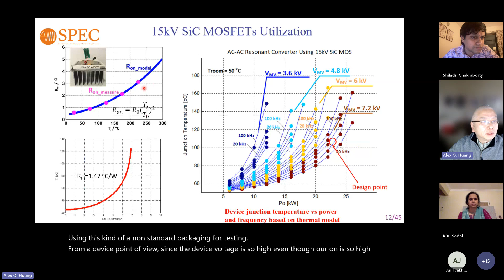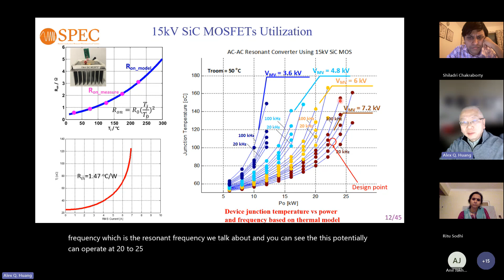The important thing is device voltage utilization - if you can increase the voltage, the same power will mean much less current. This is the optimization chart showing the utilization of the devices. What is changing is the switching frequency, which is the resonant frequency we talked about. You can see this potentially can operate at the 20 to 25 kilowatt level. The semiconductor you have here is only 2 very small 15 kV devices.